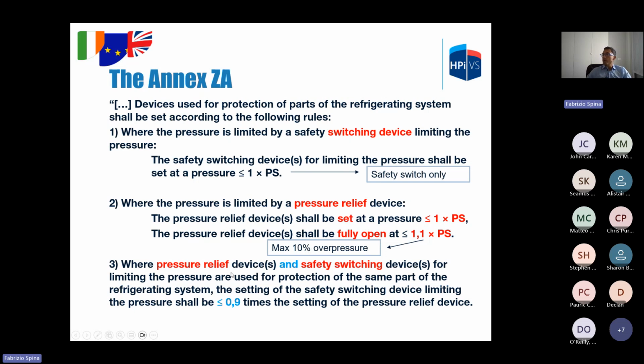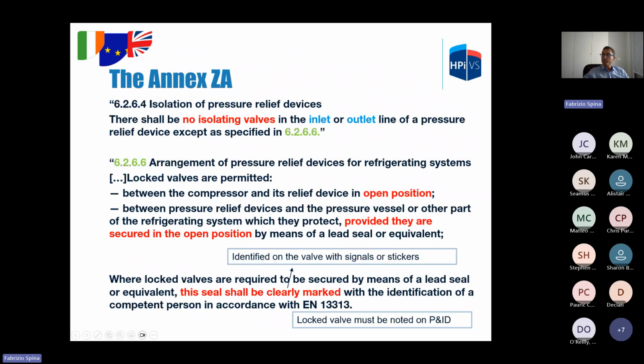When pressure relief devices and safety switching devices are installed, the switching device must be set at 0.9 times the setting of the relief valve. We usually have the situation where the pressure relief valve is set at the same value as the PS, and the safety switch, the pressure switch, is set at 0.9 the PS.